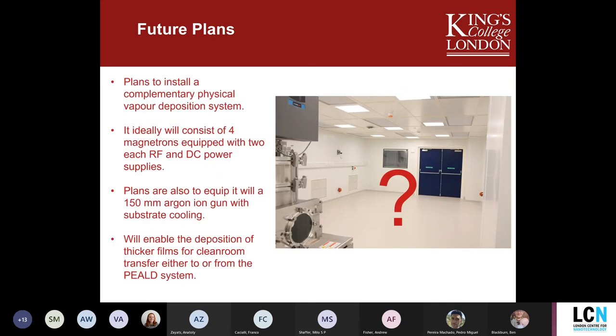For future plans for the clean room, we plan to install a complementary physical vapour deposition system. PEALD is really only suitable for a few tens of nanometres at most for some materials. We're hoping for a four-magnetron system with two RF and DC power supplies, equipped with a 150-millimetre argon-ion gun and substrate cooling for ion milling. This will enable deposition of much thicker films, and we're hoping to do pulsed DC sputtering as well. If anyone within the LCN has any comments on the specification for a future magnetron-based machine, please do get in touch — we're still hoping to secure the funding.